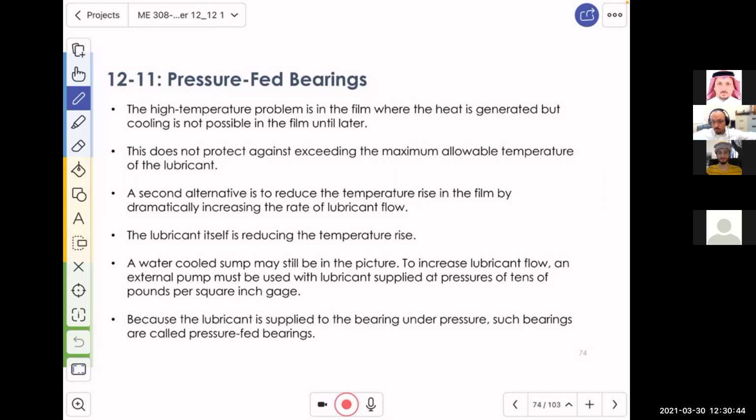The sump, the container, everything around might be at normal temperature, but remember, oil passes through that, and if the oil loses its characteristic, whether it is viscosity or other, then there might be overheating or friction or something which will damage the whole bearing.